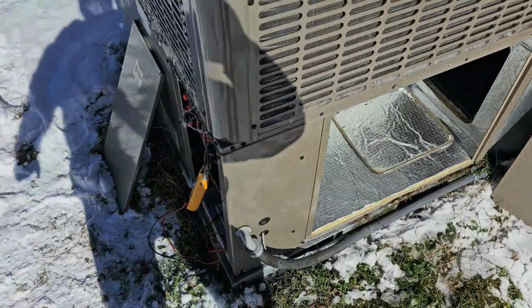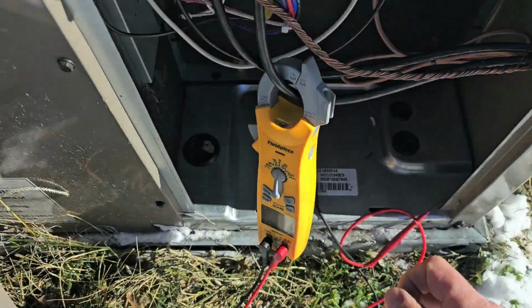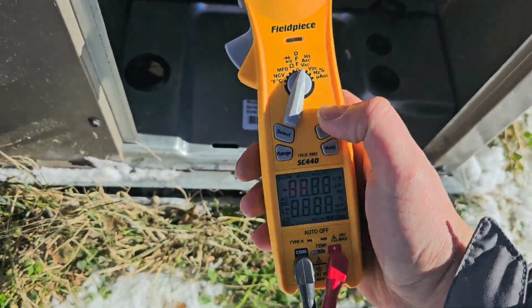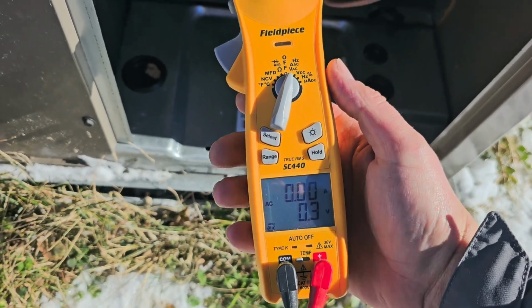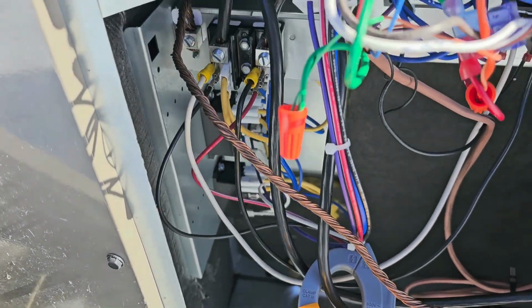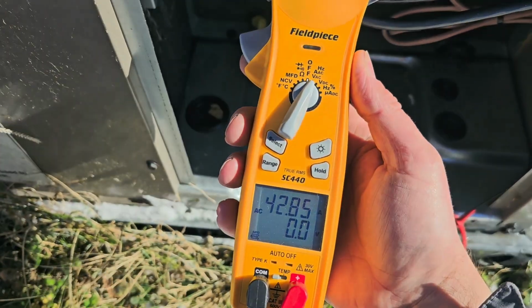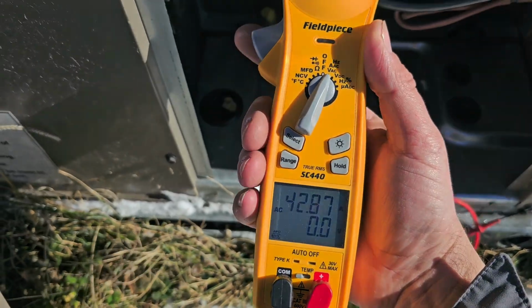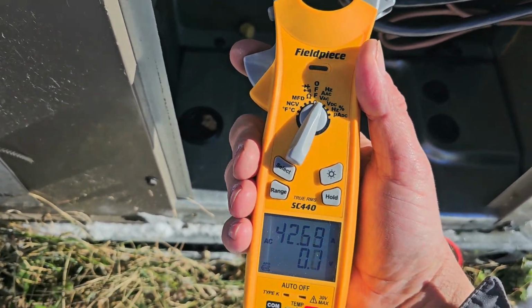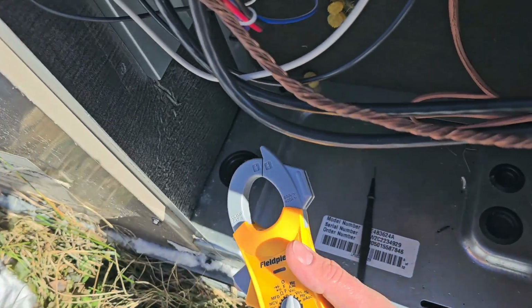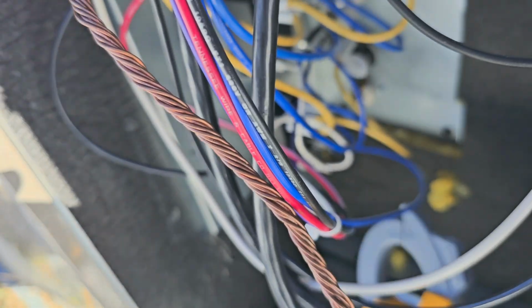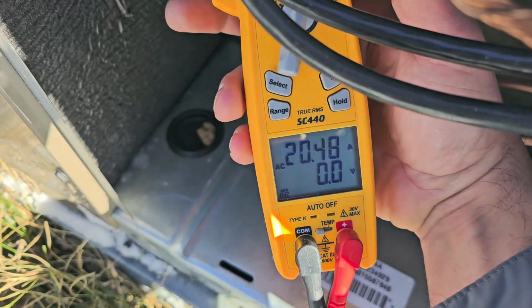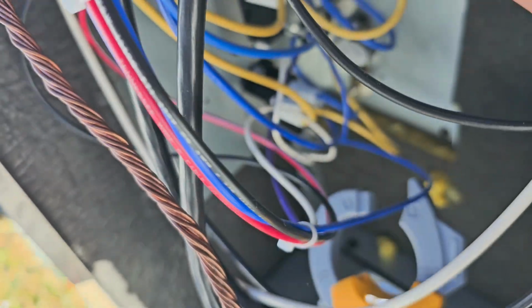You can see some discoloration in the coils of wire. I'm going to turn my meter to AAC, hit the select button, and we're measuring the main power, one side of the main power that comes into this unit, 42 amps. That means our heaters are working. So both heaters are working, but we're gonna measure individually. We'll go around this wire first. Should have about 20 amps there. And then we'll go around the, it's hard to see, the next wire.